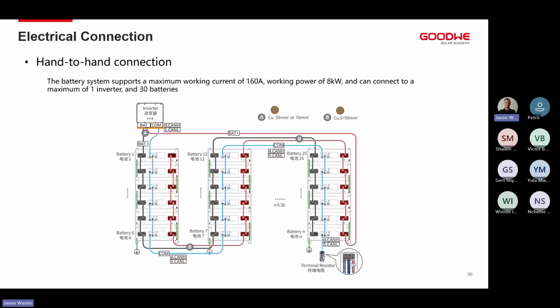This is just some of the electrical connections. The first one that we'll look at is hand-to-hand connection. Hand-to-hand connection is 160 amp working current. We can connect up to 30 of these batteries together. So this is just connecting the batteries from battery to battery, no busbar or anything like that. Negative on the first battery going into the inverter, positive from the last battery going into the inverter, and everything connected in between.